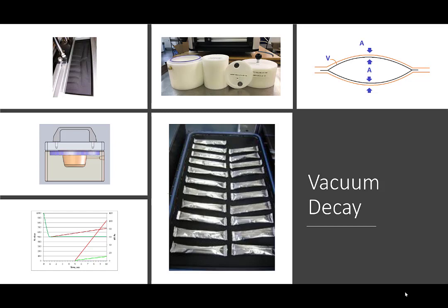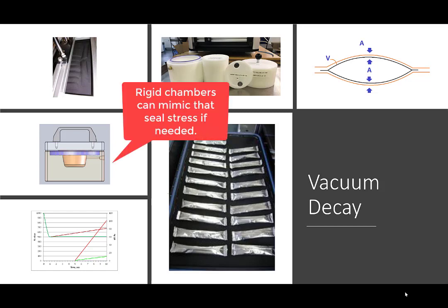If you want to apply stress on a package format, we can design a test chamber to fit the package and allow for that expansion and put that stress on the package to match a water bath and to simulate an altitude type test as well.